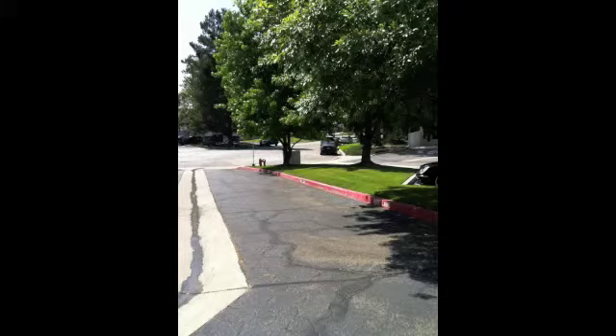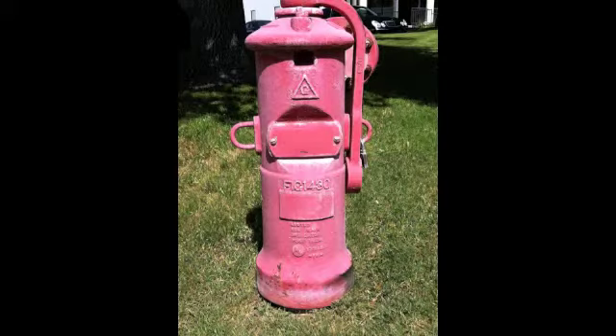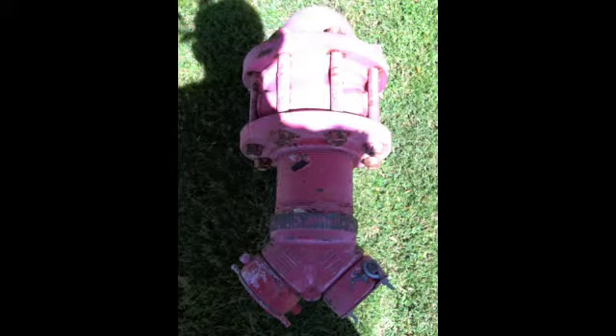This is our designated fire lane where most likely a truck company would park in case of a fire. This is our post indicator valve and second way to close the sprinkler system and shut off the water. It is in the open position, which you cannot see due to being painted over. But to close it, you remove the lock and use it as a wrench to close the valve. Behind the post indicator valve is the FDC, the fire department connection, where the fire department can hook up a hose to keep water flowing through the sprinkler system.